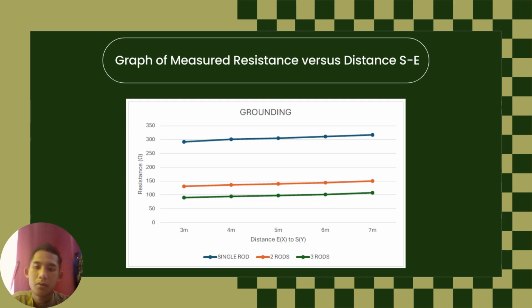So I will explain the distance factor. If you notice, all three lines have a slight upward slope. This indicates that as the distance between the electrodes increases, there is a marginal increase in measured resistance, though the number of rods remains the primary factor in overall performance.